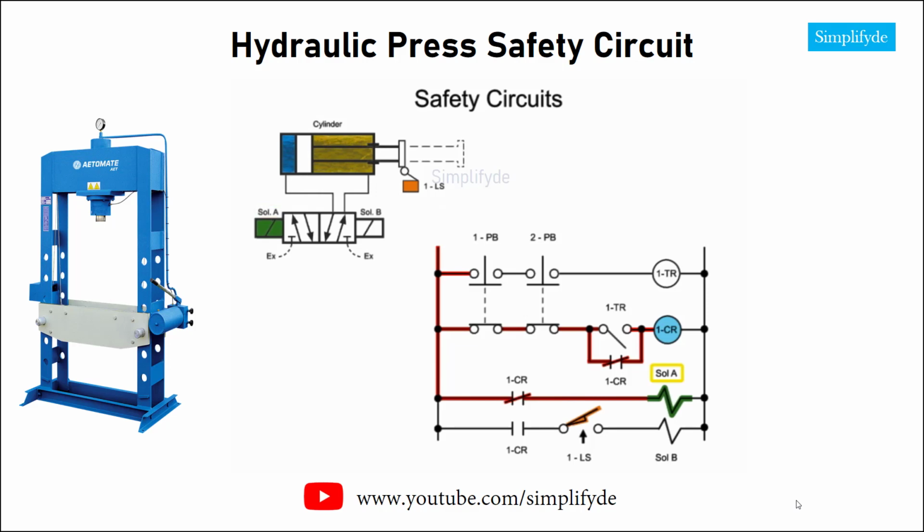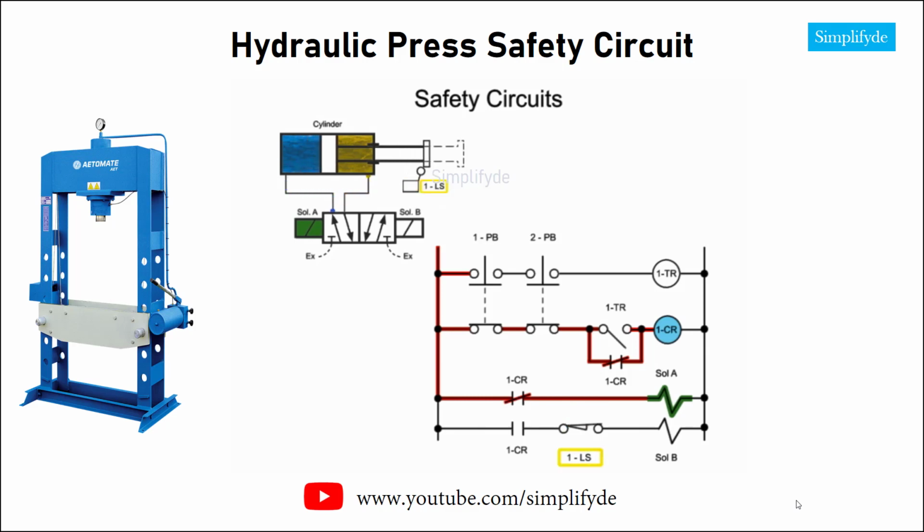Solenoid A shifts the valve to allow fluid into the blind end of the cylinder. The cylinder begins to extend, the cam releases limit switch 1, allowing it to close. At this point in the cycle, the cylinder will remain extended indefinitely until at least one push button is released. If one push button is released, the control relay will lose power, which causes 1CR to remove power from solenoid A and connect power to solenoid B.